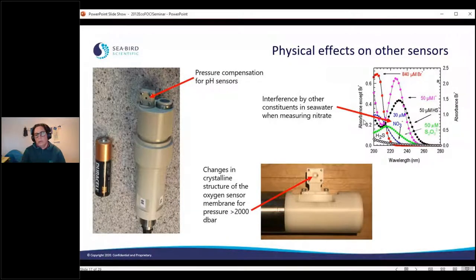And how do you understand interference by other constituents, and how do you work that out to make sure you're actually only measuring what nitrate is and not other things in the water? And then also, for oxygen sensors, if you use the membrane type sensor, the science of it is really understanding why. One problem we had, and there was a paper written about it, is why the oxygen sensor changed below 2000 meters. It turns out there's a Teflon membrane, and once you get to those kinds of pressures, the crystalline structure of that sensor actually changes. So we make a correction for that, and we figured out what that correction is and how you make it. That's kind of all the science pieces here.